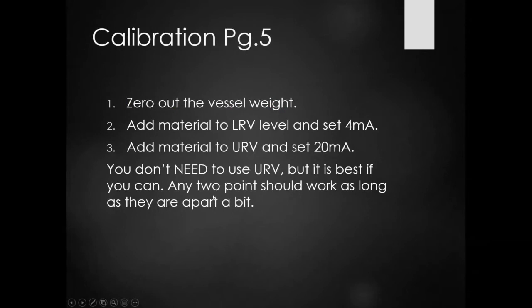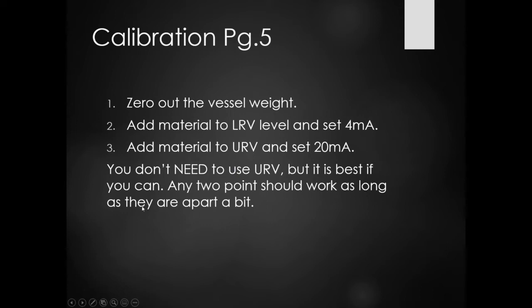Calibrating a load cell is pretty simple — if you've used a scale, that's basically the process. Zero the vessel weight, get a tare measurement, add material to the lower range value and set your 4mA, then add material to the upper range value and set your 20mA. That's ideally the best way to do it. Any two points should work as long as they're spread apart a little — you can go 25% and 50% and get those numbers. Because they're resistive, they should be relatively linear.